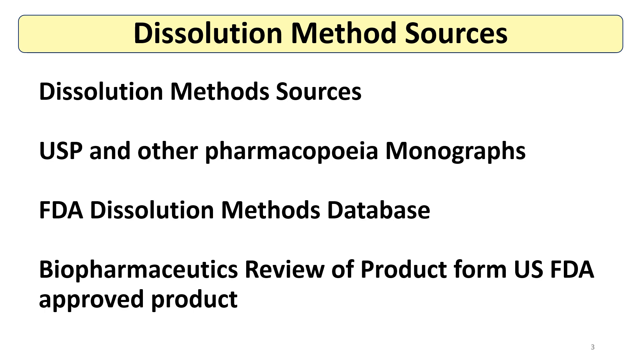Generally, the Dissolution Method is taken from the USP Monograph or the FDA Dissolution Database, called the OGD Database. Sometimes the biopharmaceutics review of the approved product is taken from the US FDA site and referred to as a starting point for Dissolution Method development. The main sources are USP and other pharmacopoeia monographs, the FDA Dissolution Method database, and the biopharmaceutics review of the drug product — where the innovator or reference product manufacturer provides information regarding the Dissolution Method.